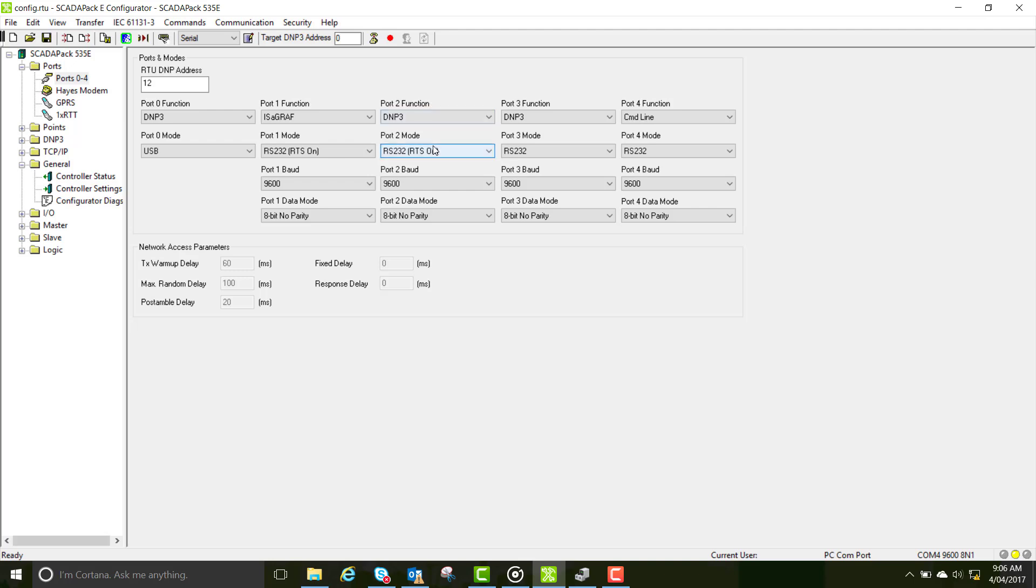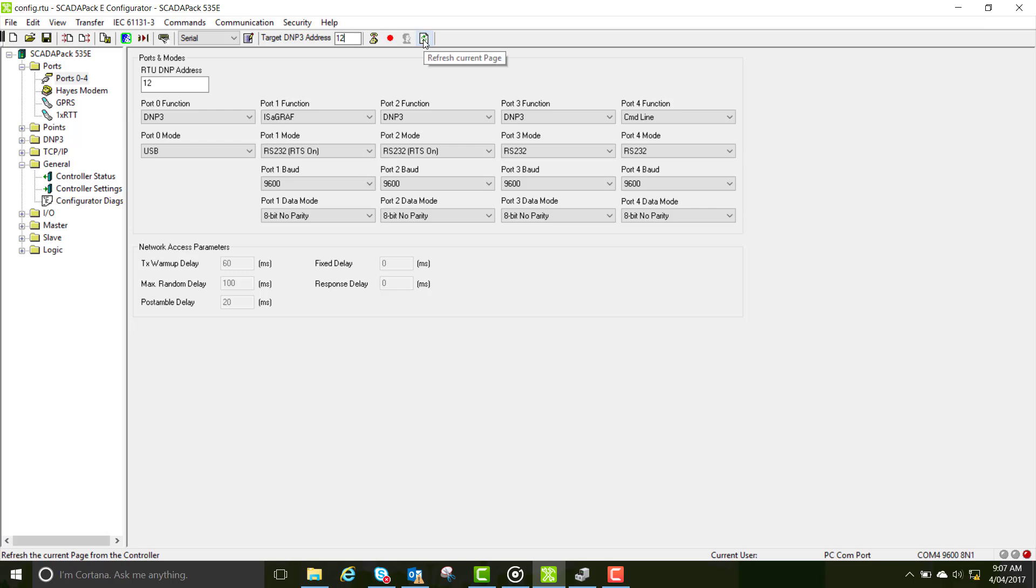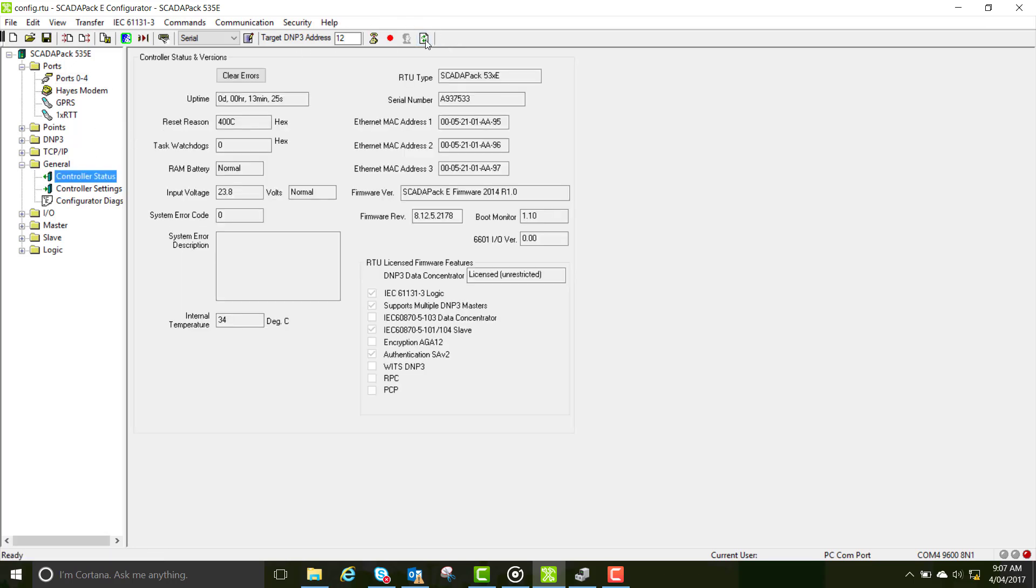Try to refresh your page and you'll notice the traffic lights down the bottom go yellow and don't return to green, so cancel your transaction. The reason for this is you haven't updated your target DNP3 address. Update this, then go into controller status and refresh your page again and you'll see the traffic light has come back to green.